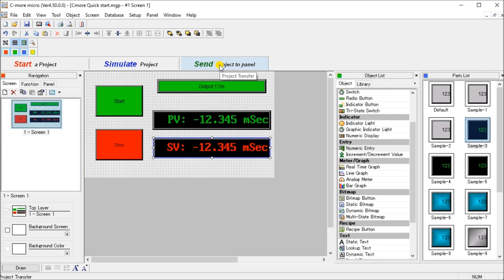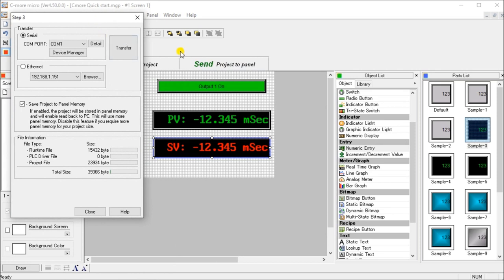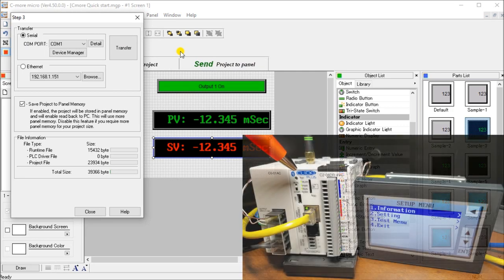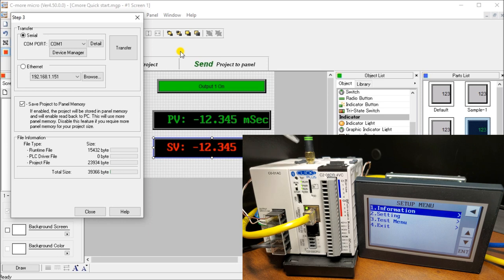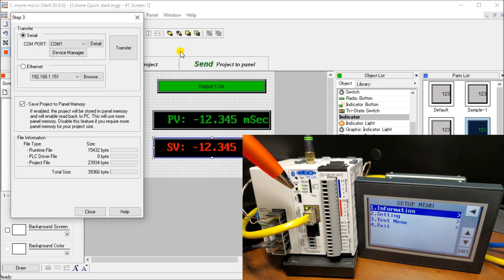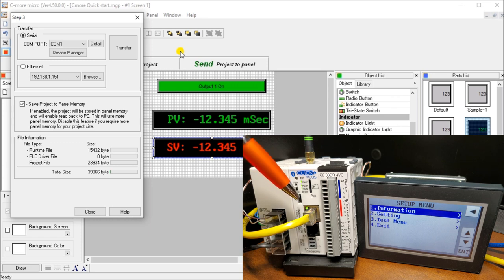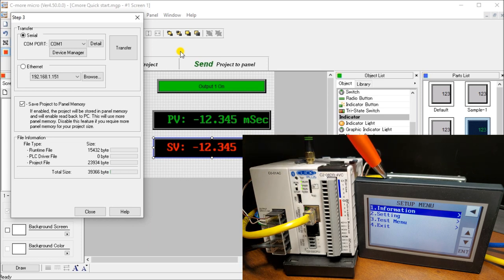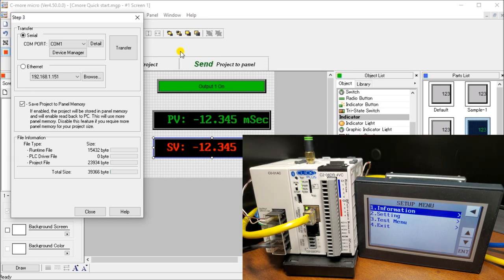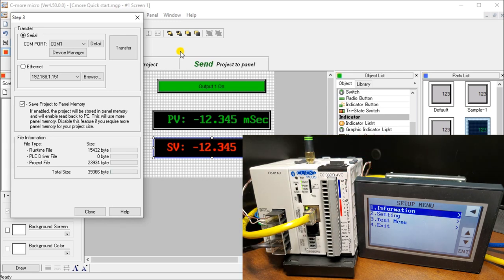And the next thing we'll do is actually send this information down to our hardware. Here we go. So let's actually take a look at our hardware that we have here. And here we go. And you will see that we have our Click plus PLC right here. The one that we've already programmed the information for. And we can communicate Wi-Fi or we can communicate Ethernet. We're actually doing Ethernet right now. Because the screens send a lot of information back and forth. And that's critical. I would always recommend that we actually use a physical hardware to actually communicate to those screens. Then we have our actual screen itself. And this is an EA3-T4CL. So we are communicating Ethernet to it. And when we first power it up, you'll see that there's no information, no memory. So it looks like this. It brings up the setup screen.